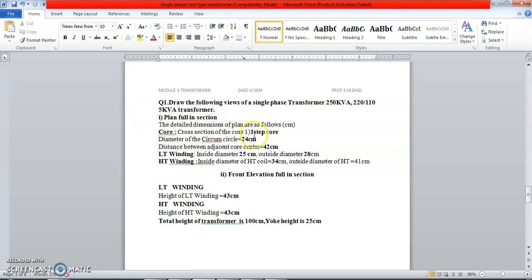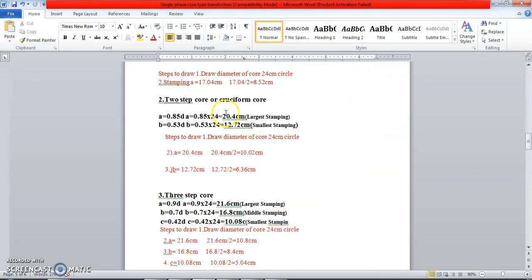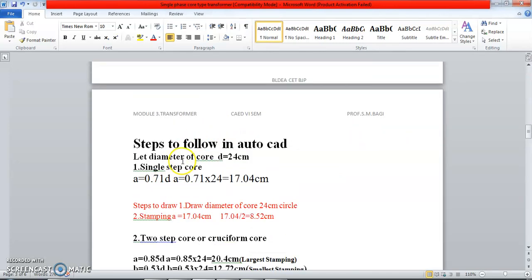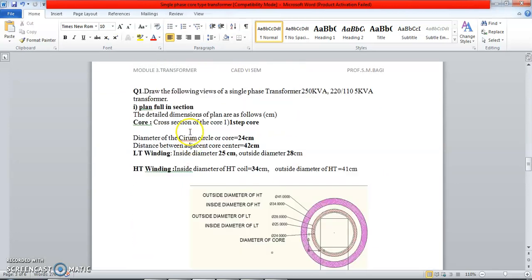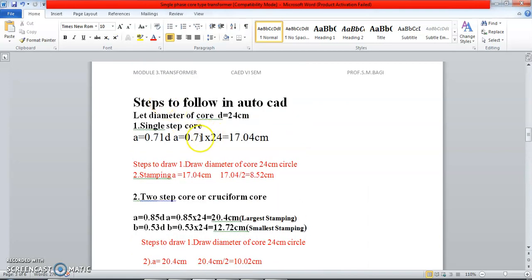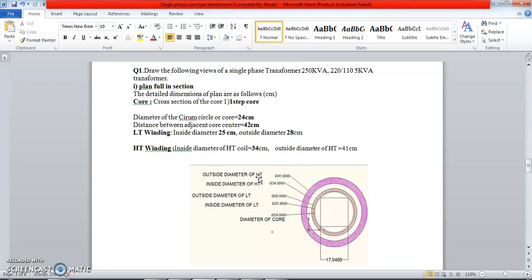The single-step core formula you have to remember is: a = 0.71D. In this problem, the specified diameter of the core is 24 centimeters. So substituting: a = 24 × 0.71 = 17.04. Making it half gives 8.52, because that value is used in the plan. I already discussed that, so now I'll go for the elevation section.